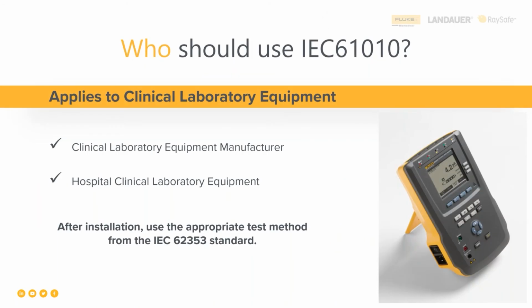All right, we talked about IEC 61010 already. It's intended for the clinical laboratory equipment manufacturer. It is for the installers of that equipment in the hospital or the clinic or the freestanding clinical laboratory. And once that installation has been done and documented using the IEC 61010, and the equipment goes live, that is, begins to be used, from that moment on, we will do repeat testing using IEC 62353. So the 61010 only applies to the medical device or the clinical laboratory equipment manufacturer and their installers. That's all. So unless you're working in that part of medical devices, then you would simply use the IEC 62353.